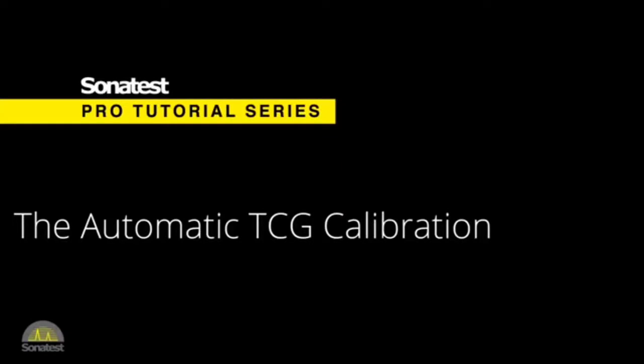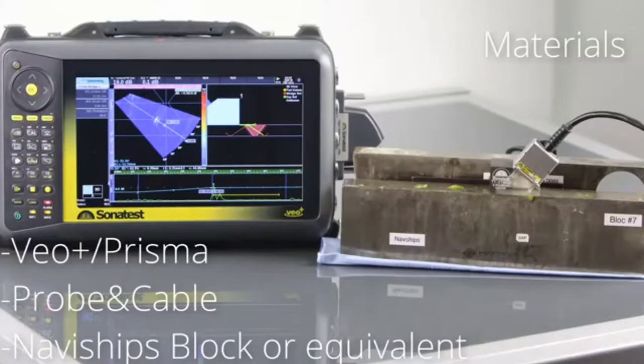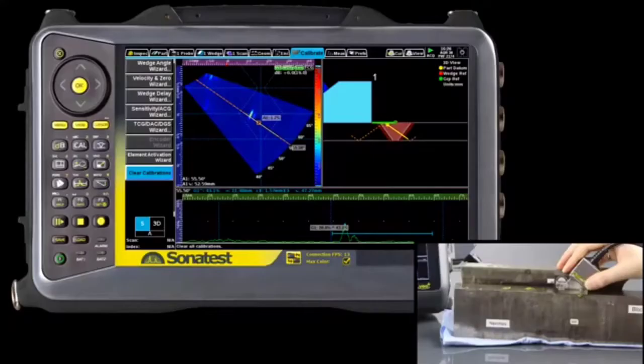For this calibration, you're going to need a VEO Plus or Prisma, a probe and cable, and a navship block or equivalent TCG block. We are using the same wizard principle as shown in earlier tutorials. In this example, we select a 2.25 meg probe and we add a 3D view to our inspection setup. As you can see, all the calibration markers are green and the TCG is the last calibration to be set.